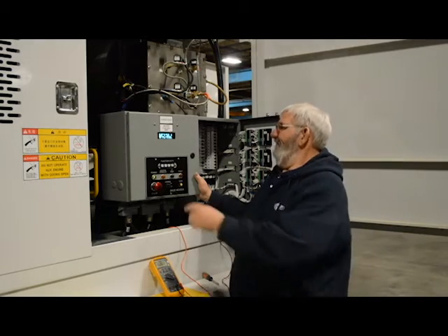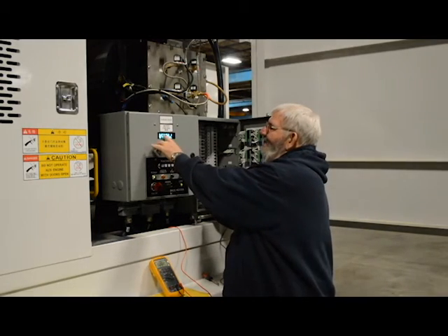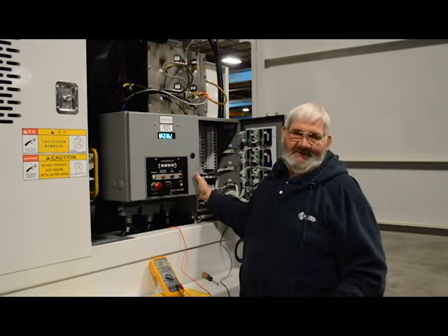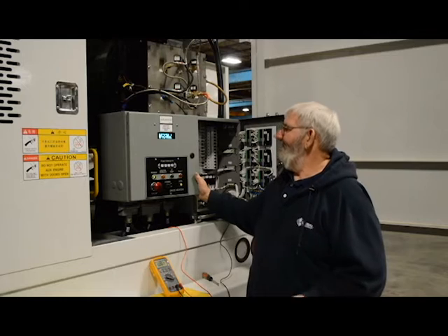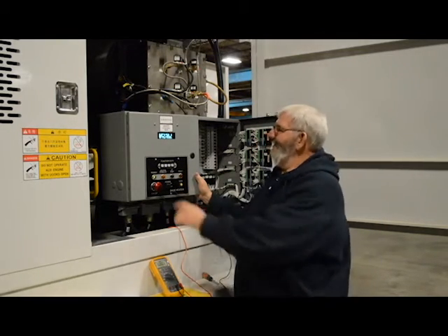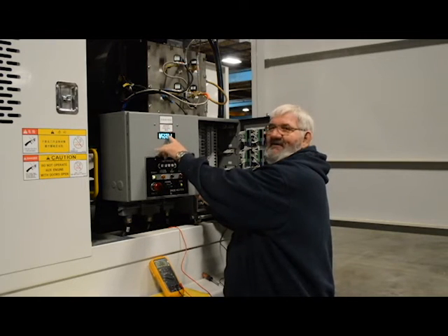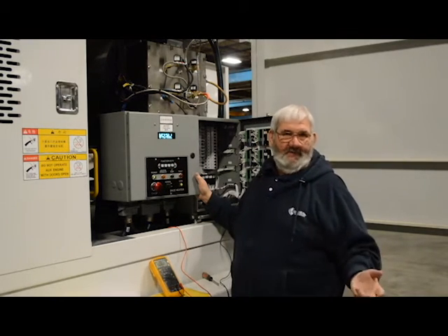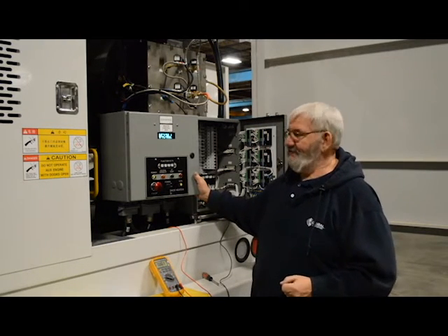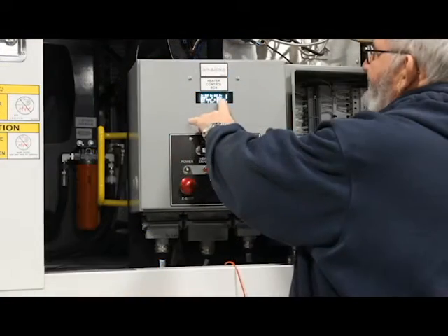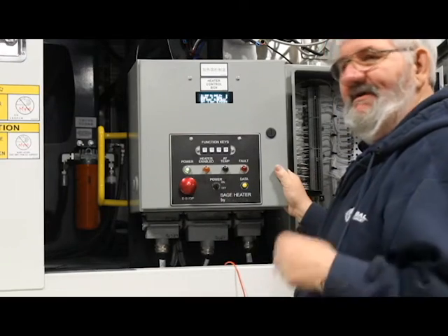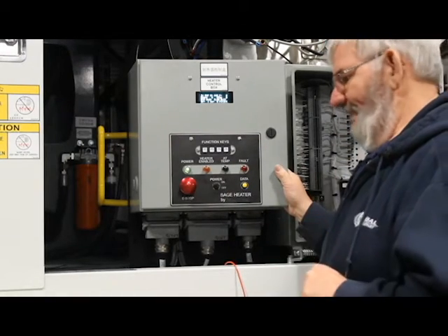If it was shorted on the inlet side, this number would be a lot lower, like minus 150 degrees, just for example. The same thing with your outlet side. The number would either be high or low, depending on if it was open or shorted. Also, your fuel pressure transducer would be the same. The number would be higher or lower, depending on if it was open or shorted.